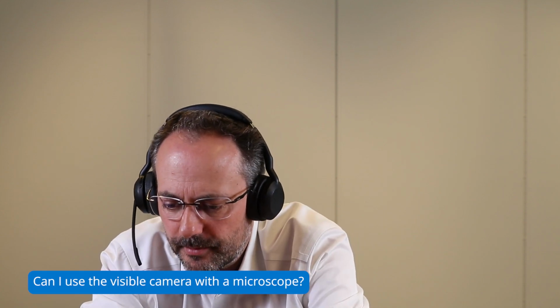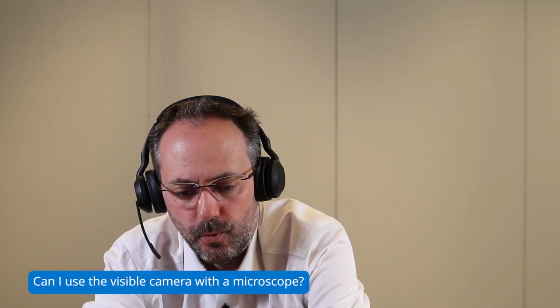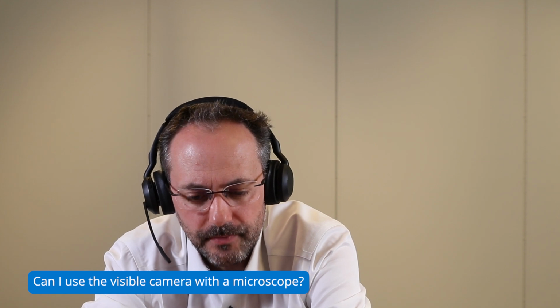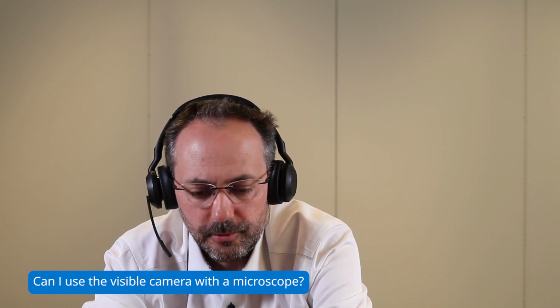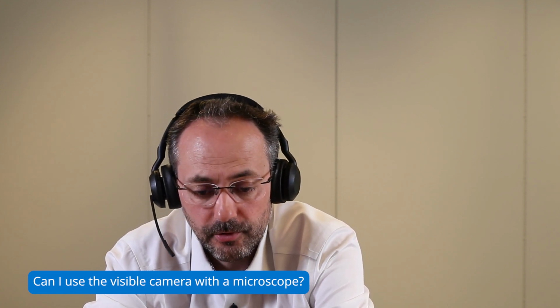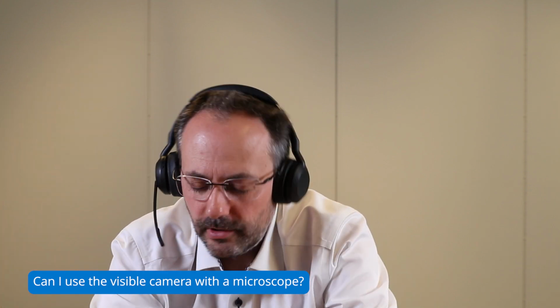Can I use a visible camera with a microscope? Yes, we have a C-mount adapter. And with the C-mount adapter, if your microscope has a C-mount adapter as well, then you can put the camera on it. The only thing you have to take into account is the transmission of your microscope. Is it really between 400 and 1000 nanometers, or does it stop at 700 nanometers? We had customers telling us that the camera is not working after 800 nanometers.